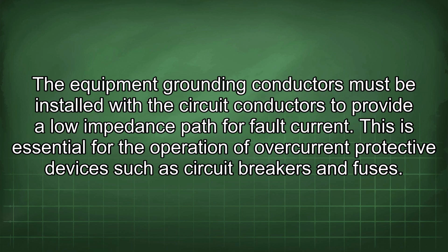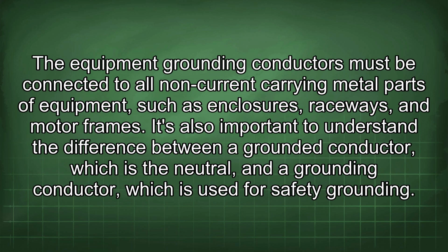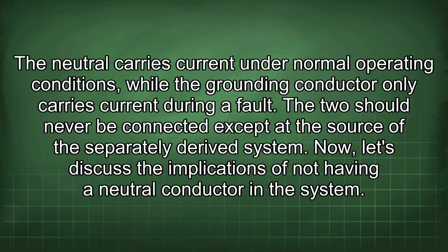The equipment grounding conductors must be installed with the circuit conductors to provide a low impedance path for fault current. This is essential for the operation of overcurrent protective devices such as circuit breakers and fuses. The equipment grounding conductors must be connected to all non-current carrying metal parts of equipment, such as enclosures, raceways, and motor frames. It's also important to understand the difference between a grounded conductor, which is the neutral, and a grounding conductor, which is used for safety grounding. The neutral carries current under normal operating conditions, while the grounding conductor only carries current during a fault. The two should never be connected except at the source of the separately derived system.